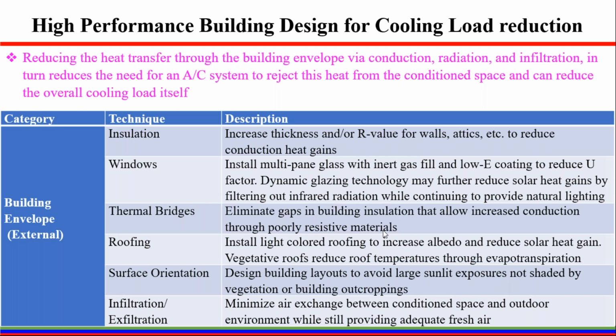If the roof can be insulated, the overall air conditioning requirement can be reduced. Surface orientation: if your building is oriented towards the south side, you may increase the overall air conditioning load, and you can reduce the overall air conditioning load if the building is rightly oriented. Infiltrations: through door spaces and window spaces, a lot of outside air can come inside the air-conditioned room. That can be reduced by proper sizing of the windows and insulating the windows and the door spaces to reduce the outside air.